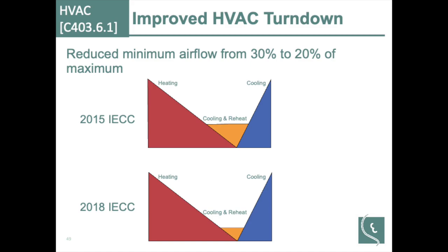Does this apply when you have demand control ventilation? Yes, demand control ventilation is independent of the variable air turn down. Now the demand control ventilation may actually ramp this up because you need more than the minimum. But this is really saying, what is the minimum the system should be capable of getting to, or should the particular zone be capable of getting to? So there may be individual cases where you'll end up being up here above the minimum.